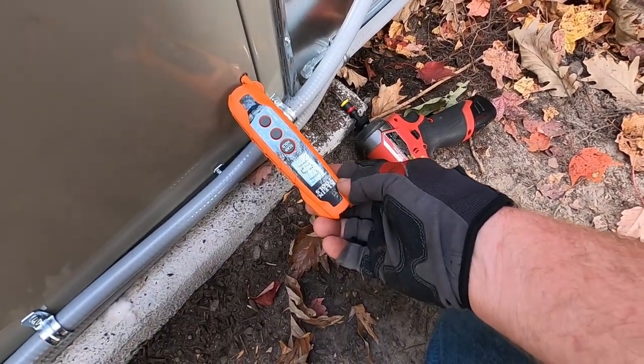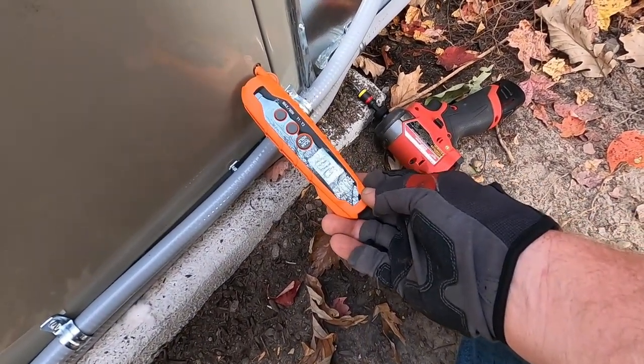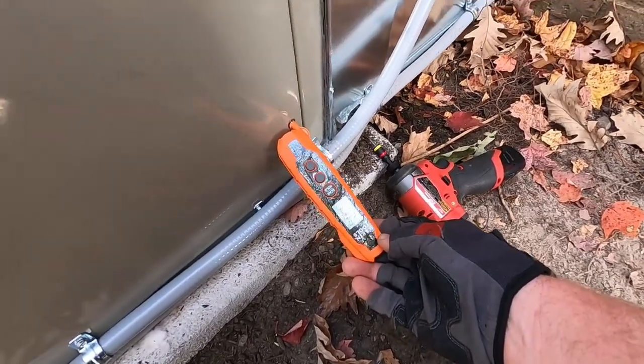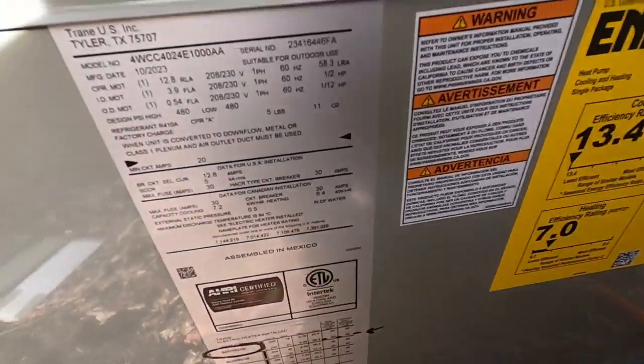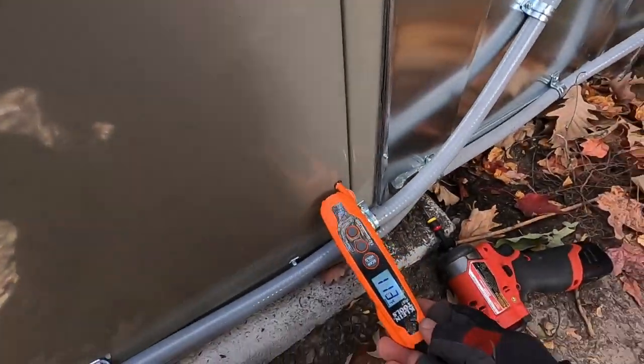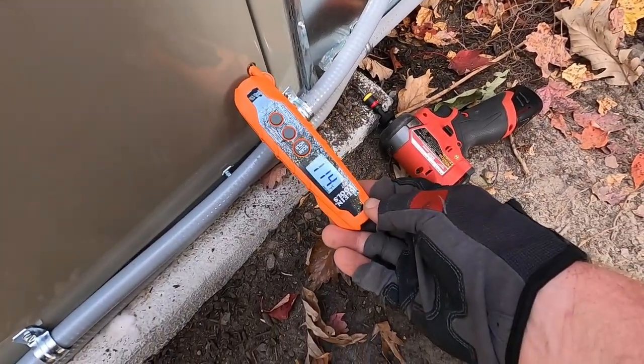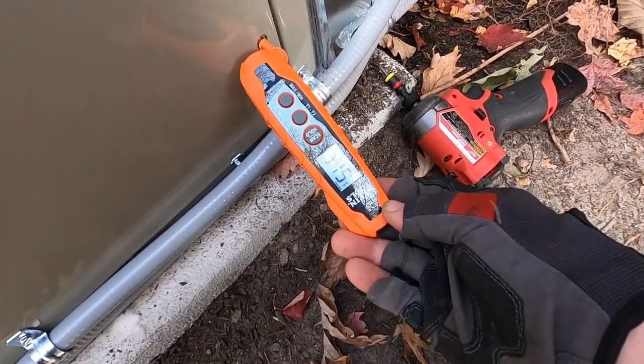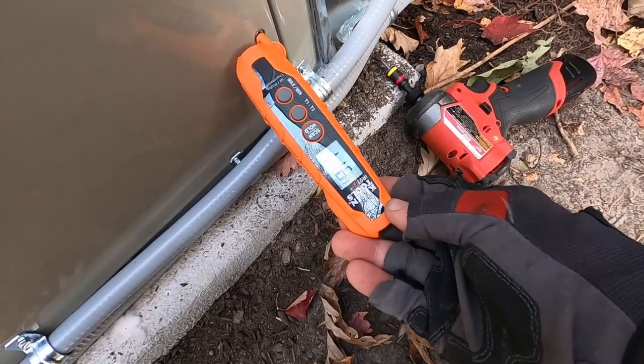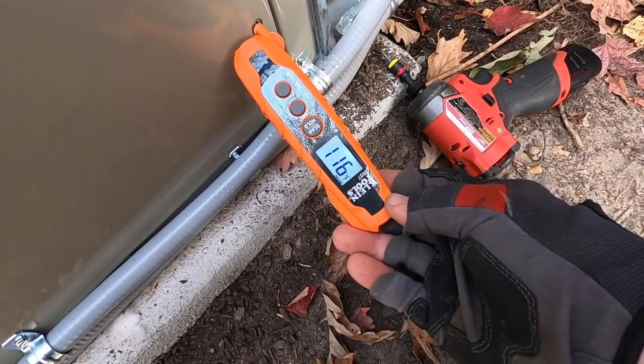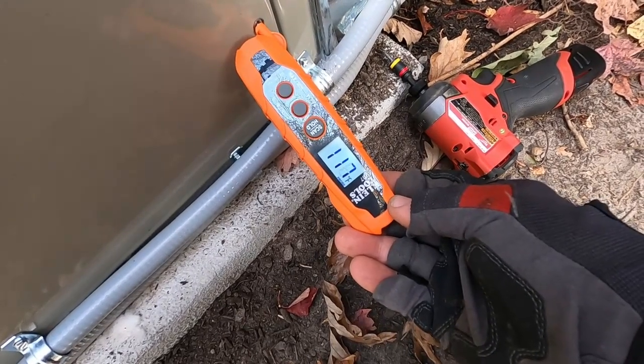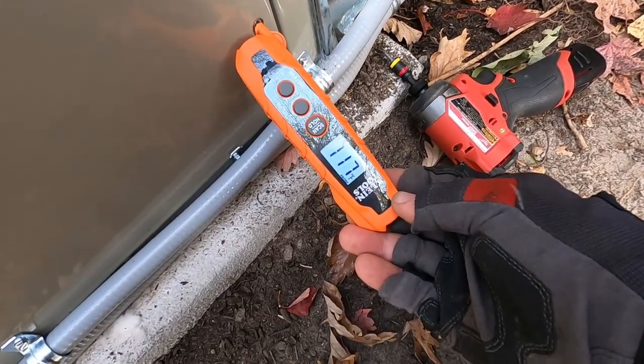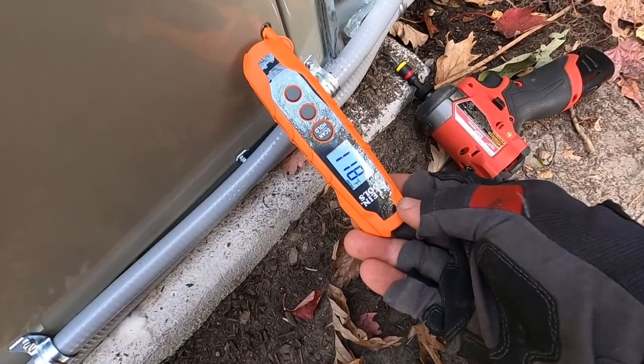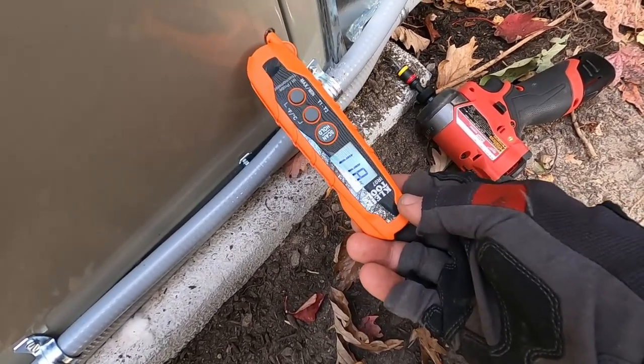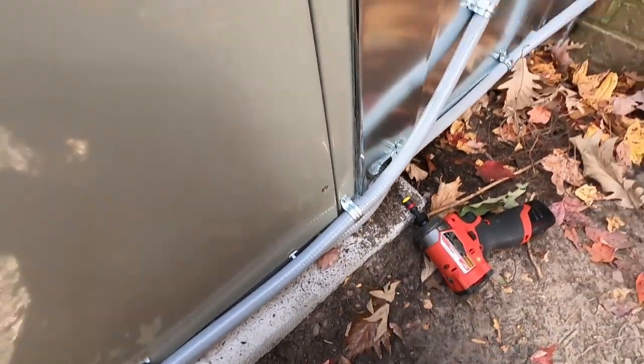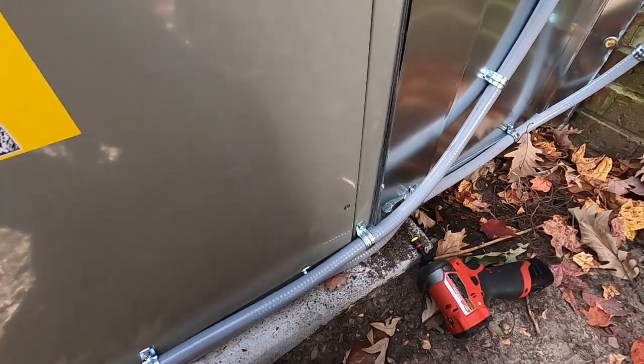Those are only 5 kW heat strips in this unit. It's kind of a smaller house. We're only looking at a 2-ton package unit. And we're up to 115, 116, 117. So we're at roughly a 47, 48, 49 degree rise on this system. So she is purring like a kitten.